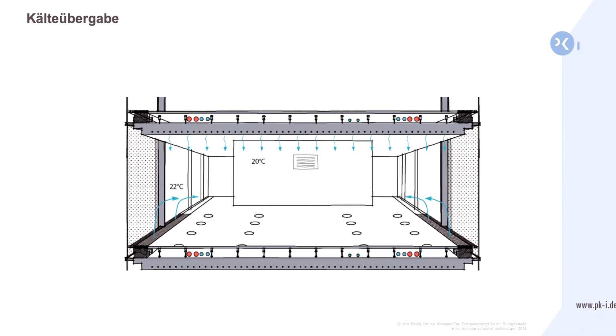Let's see it such that a highly glazed office building with its low-tech activation system, concrete core, needs to deal with. So this is the approach we need to realize, because at first glance, the building appears high-tech, but it's not a lot of air supply and air conditioning, it's just this concrete core activation in order to generate pleasant temperatures. Apart from that, the user said it's okay if we can abide by 26 degrees in summertime.